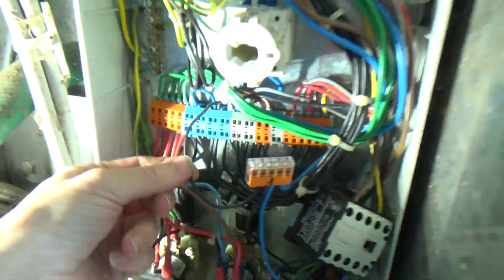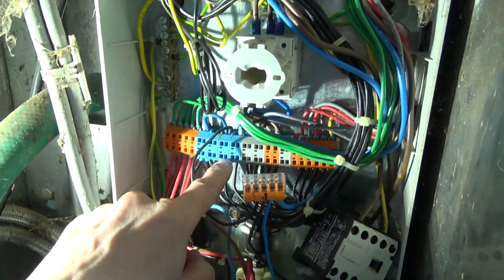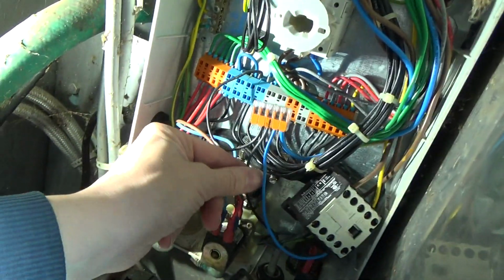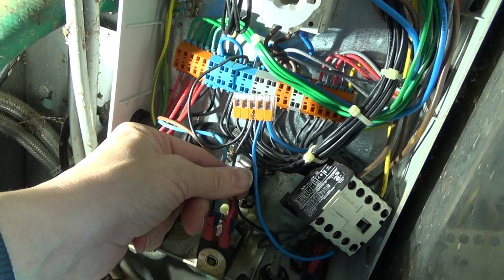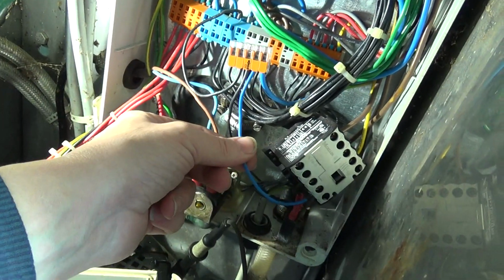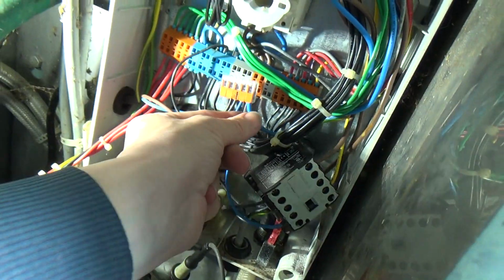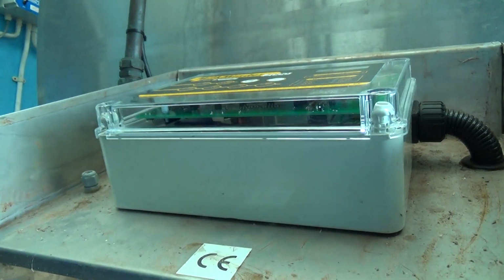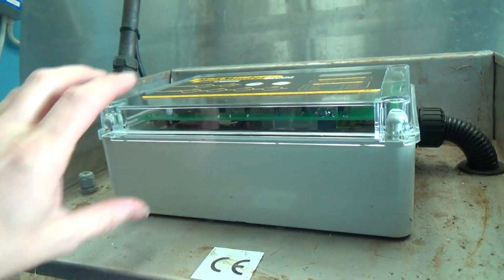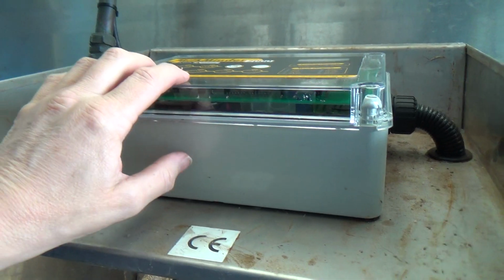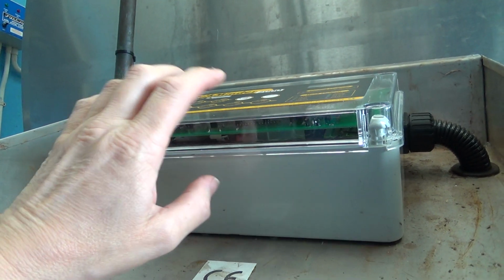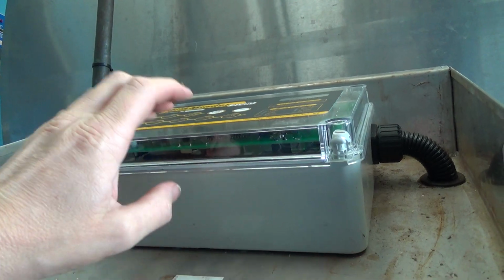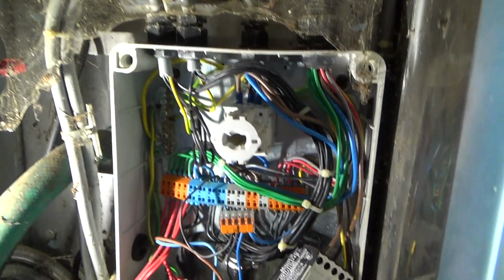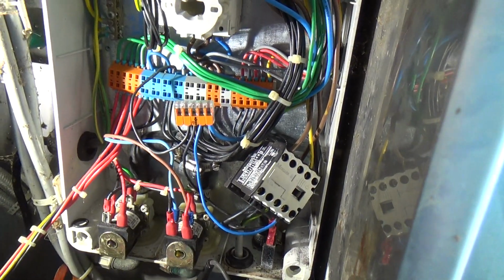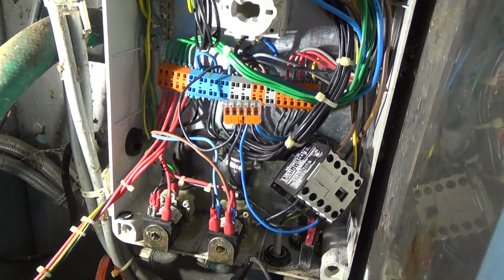Okay, that's our neutral wire to the terminals. To there, that's our neutral that does the water pump and the drain valve, dump valve. That neutral does the coil for the contactor, and that neutral does the circuit board logic, just the transformer. There's no switch neutrals in there. It's just the lives that are switched.